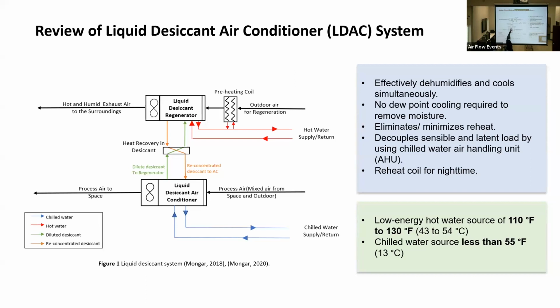We have heat recovery. Since the desiccant's going in a loop, it's coming back from the regenerator hot, and it's leaving the air conditioner, the dehumidifier, cold. Those get transferred into a heat recovery heat exchanger just to save the energy that's being required for running those units independently. And on the regenerator, which sits outside, in very cold months, we will use hot water from the CHP system there. They've got a 4-pipe system, and we'll use that to preheat the air.